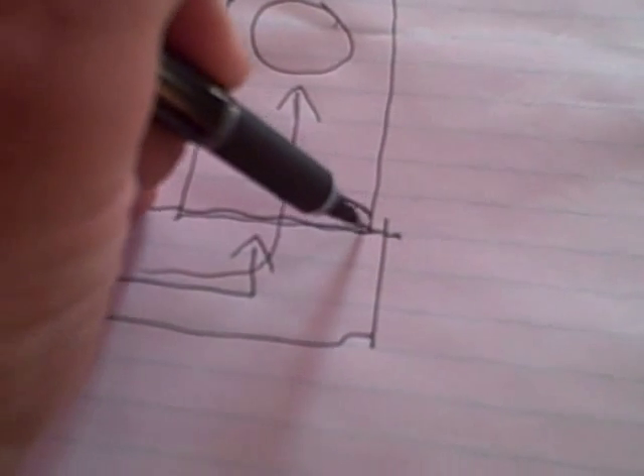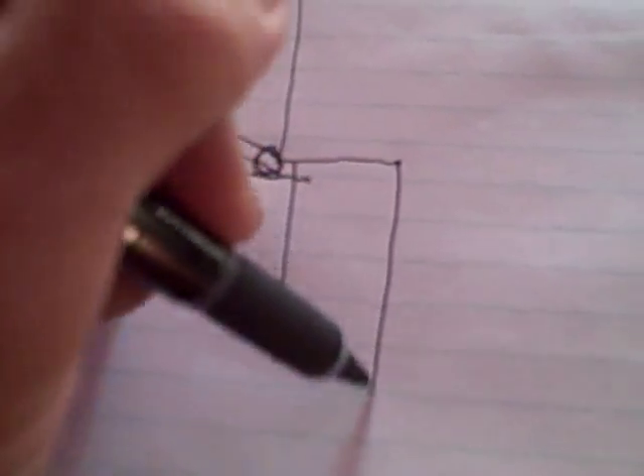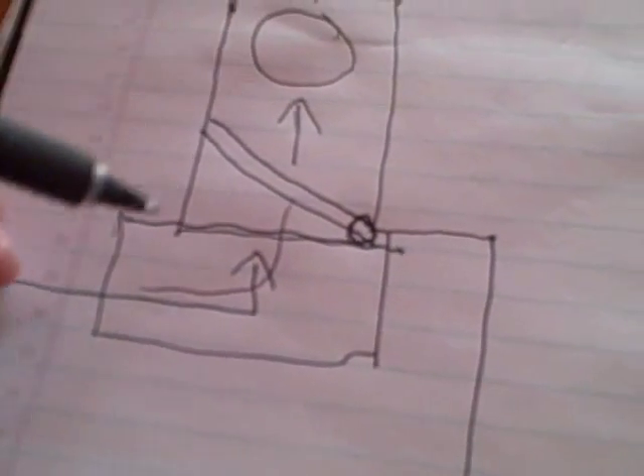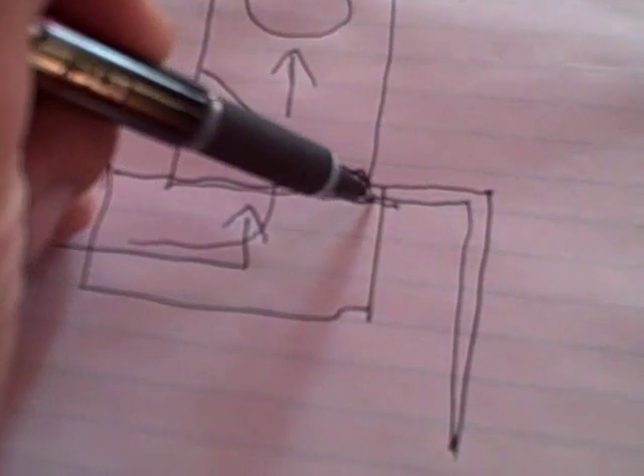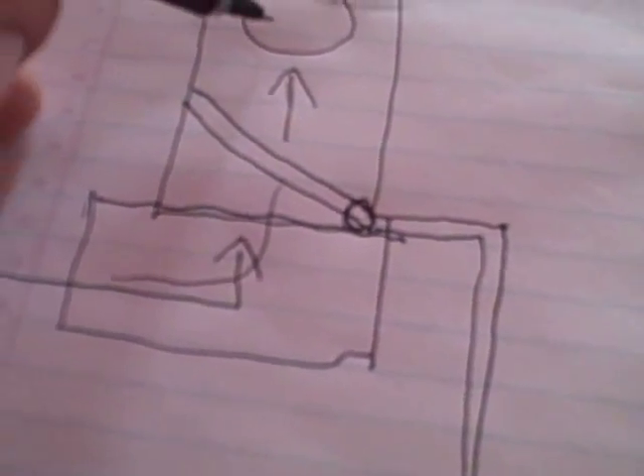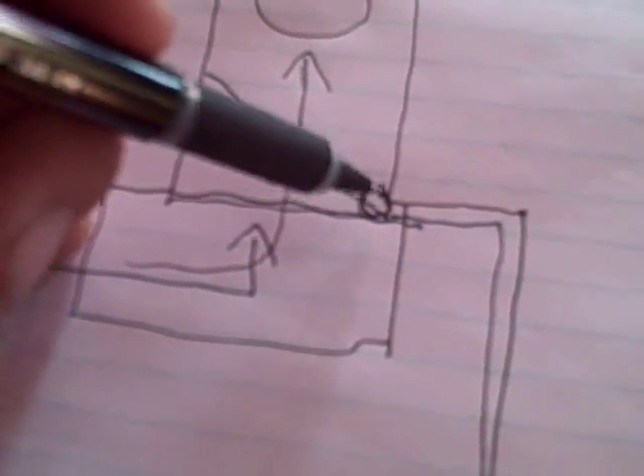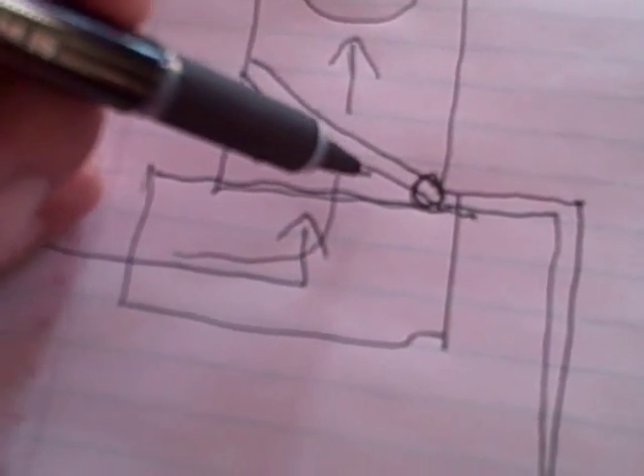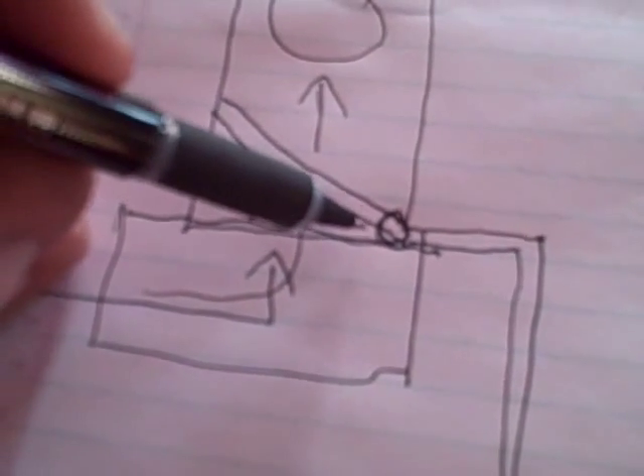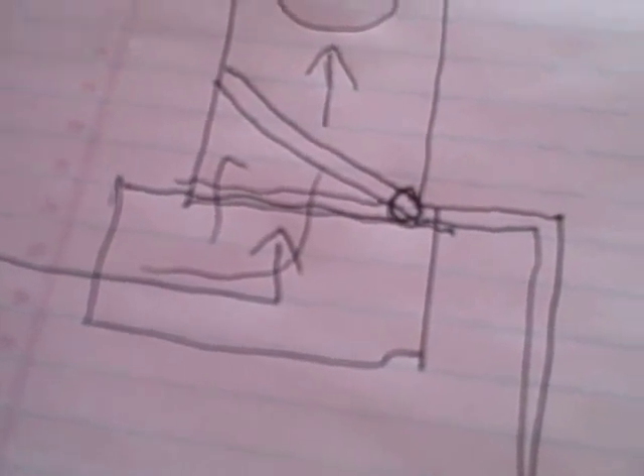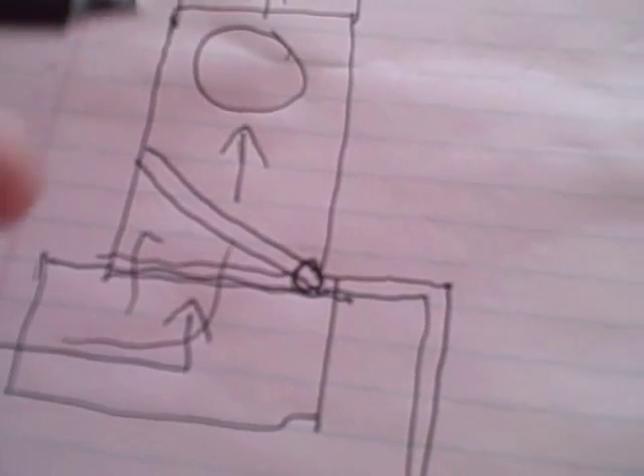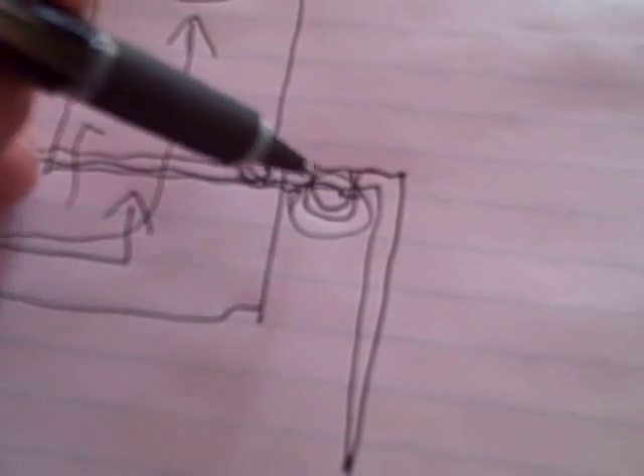Now if you have a drain line down here and it's piped straight out with no trap on it, what happens is when the blower is running - let's say it's running a long time - it's pulling air through here, but it's also pulling air up through the drain. That's a lot of air pressure, so it just sucks air through the drain and this water will bubble up in here. You can hear it gurgling. If you're lucky and it shuts off in time, it'll drain out. If you're unlucky and it's running a long time, the water will overflow the pan level and you have water all down in here. With a trap, you put a trap in line there - you have a certain amount of water that lays in the trap area all the time, which is enough static water pressure that it's not able to suck air through, but the water naturally flows down the trap.